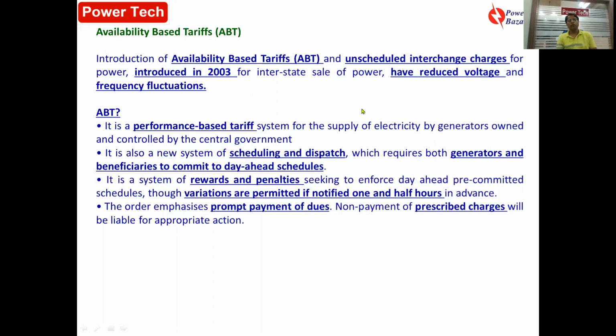In case of a power generating company, you all know energy cannot be created, cannot be destroyed, it can only be conserved. That means if a generating company keeps on generating 100 megawatt, but the load is suppose 90 megawatt, what will happen? 100 megawatt is generating, 90 megawatt is the consumption, that means 10 megawatt surplus is there. So in order to achieve power balance, what will happen? The voltage will rise because generation is more and load is low. Therefore, rise in voltage will give rise to frequency because the generator will overspeed. So frequency rise will be there, voltage rise will be there, that means the grid will not be stable.